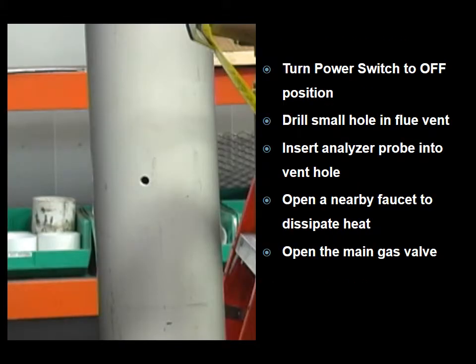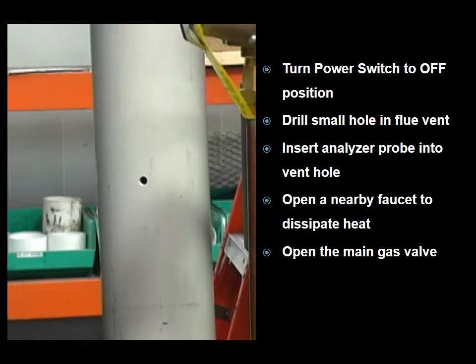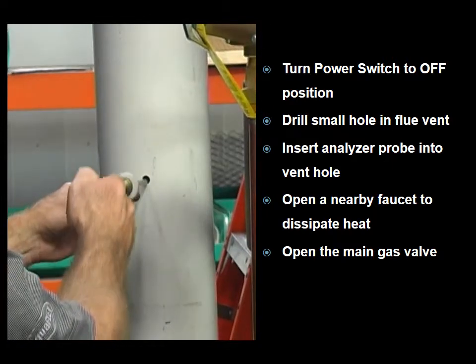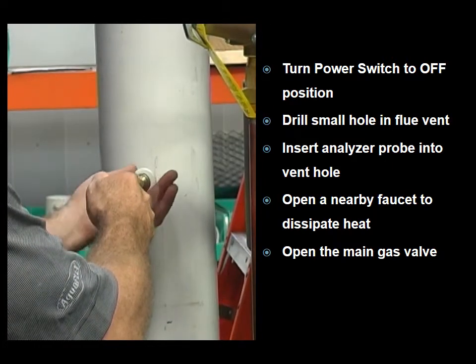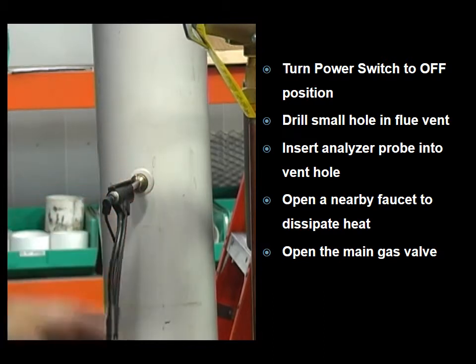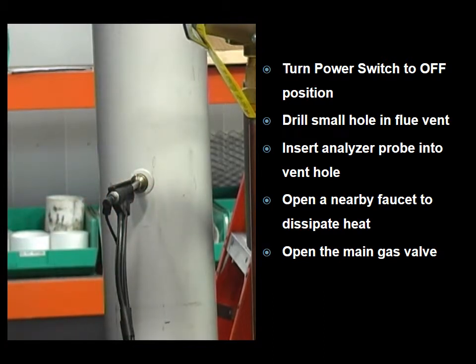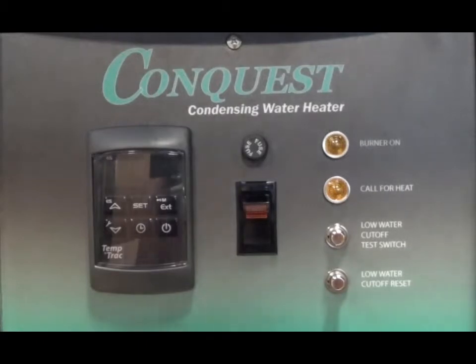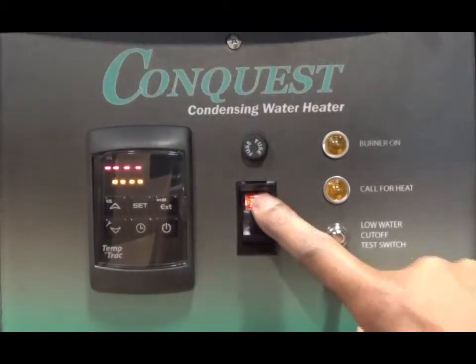Begin by turning the power switch to the off position. Drill a small hole in the flue vent approximately 2 feet from the appliance vent connection. Insert the combustion analyzer probe into the vent hole. Before starting the unit, ensure there is a way for the system to dissipate heat. This can be accomplished by opening one or more nearby hot water faucets.